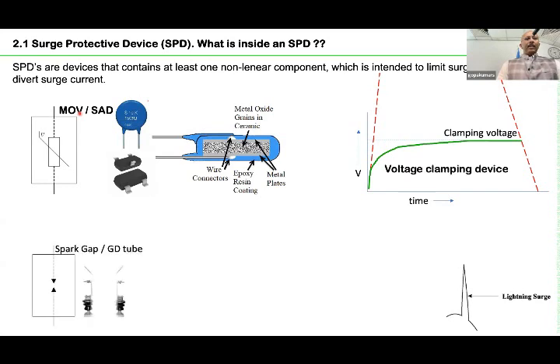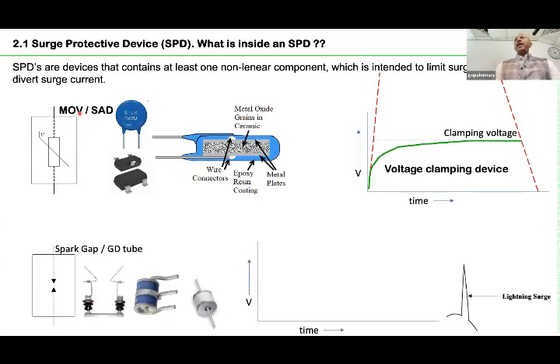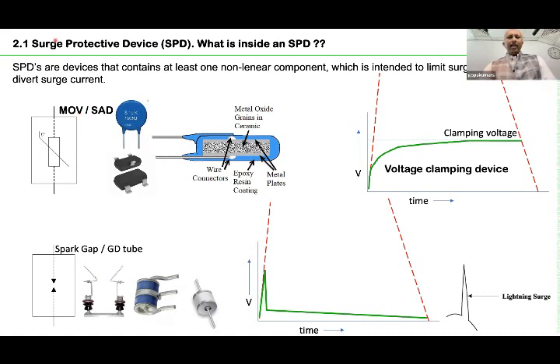Similarly, there is one more device, which is a spark gap or a GD tube, and these are called voltage switching type devices. For example, as you can see here, this green one, once the potential difference between the terminals reaches its spark over voltage, suddenly the device will act like a switch and the line and neutral are connected. So this is very important. Understanding the characteristics of the voltage clamping device and the voltage switching device is sometimes important while selecting an SPD.